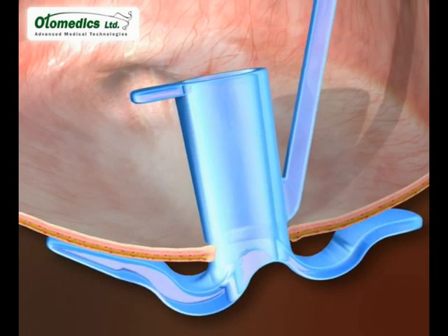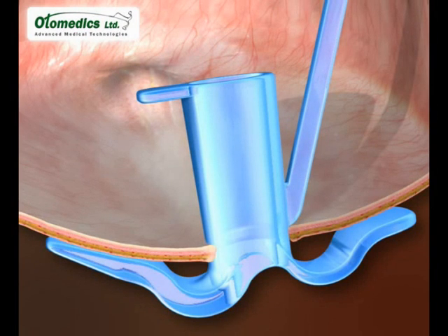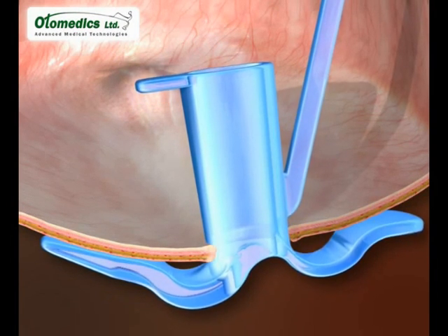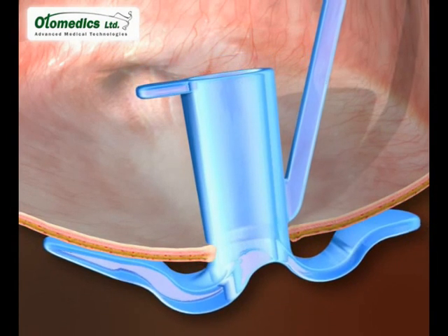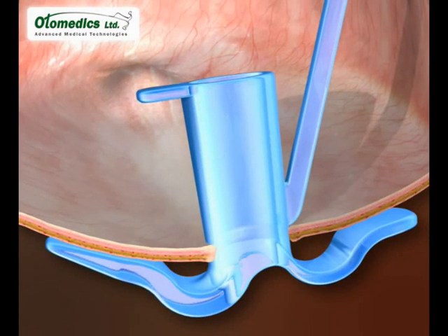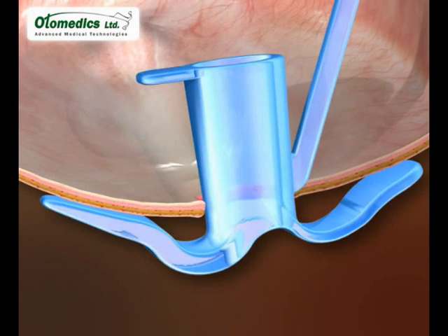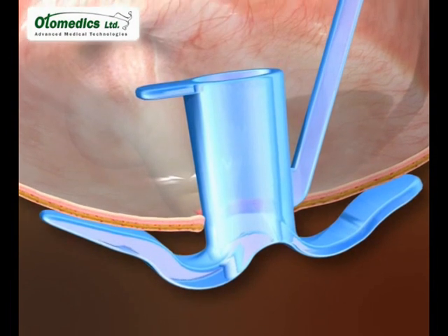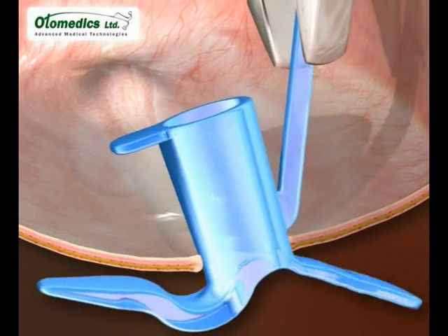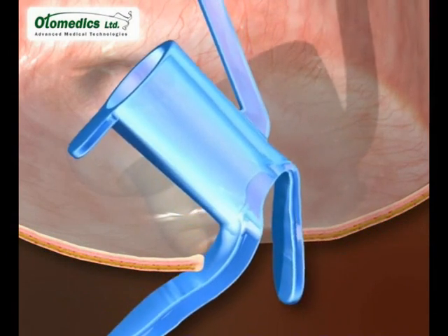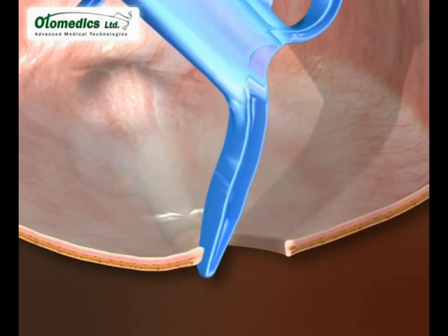This tube exempts the surgeon from making compromises. It is suitable for every tympanostomy tube insertion case, every age, and every middle ear condition — for long as well as very short term retention. When in position in the eardrum, the tube should be cleaned every few months. When the tube has to be removed, the extraction handle is pulled gently, activating the collapse mechanism, and the tube comes out easily.